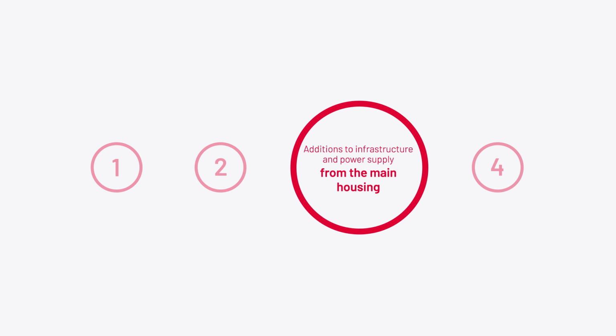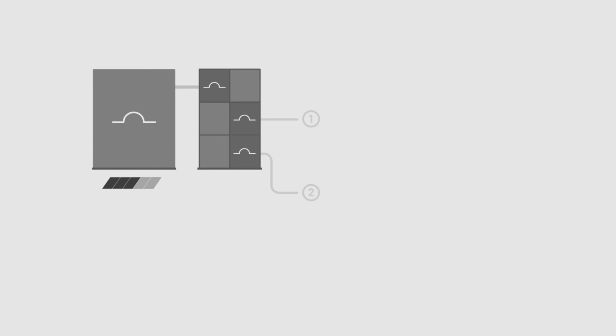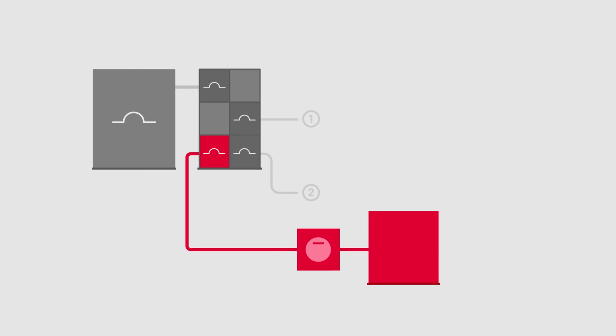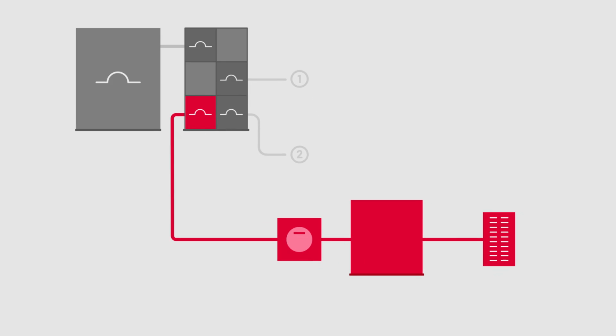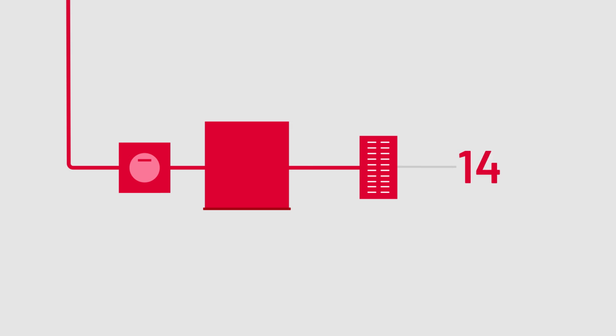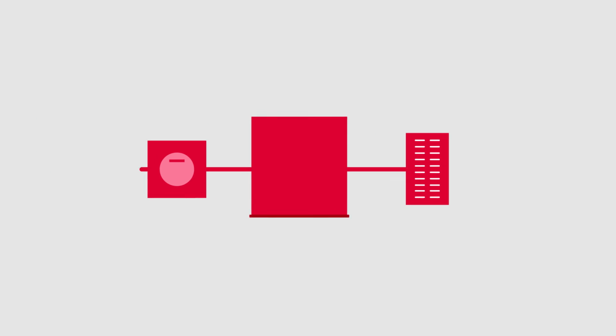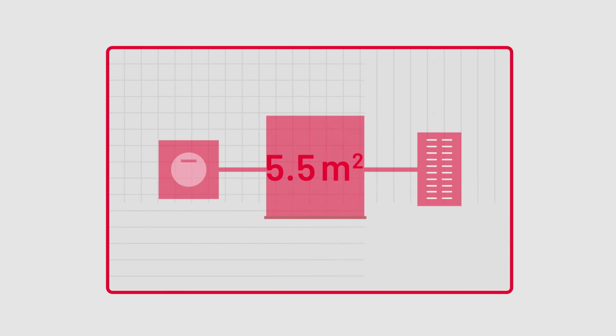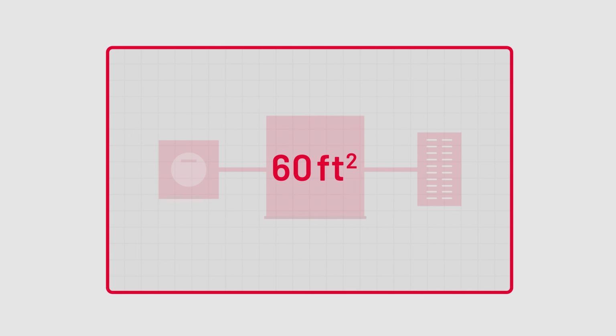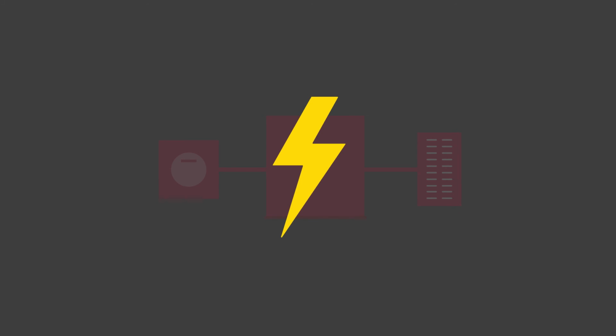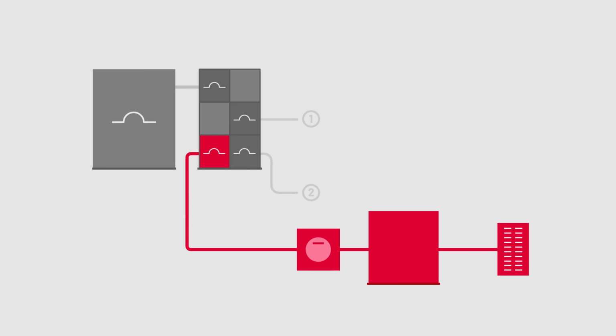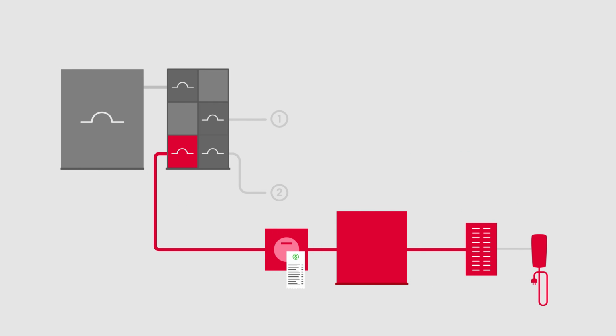Additions to infrastructure and power supply from the main housing. When the unused electrical capacity of the main switch and main housing is sufficient, it is possible to supply power from this housing to a new switch, a new meter, a new transformer, and a new electrical panel, which usually allows for the installation of 10 to 20 charging stations. However, to add these components, it is necessary to have approximately 5.5 square meters or 60 square feet of available space in the electrical room. Since a new meter has been installed, the electricity consumed by the charging stations will be billed to an independent account.